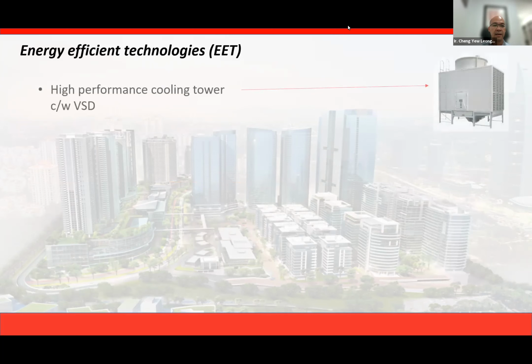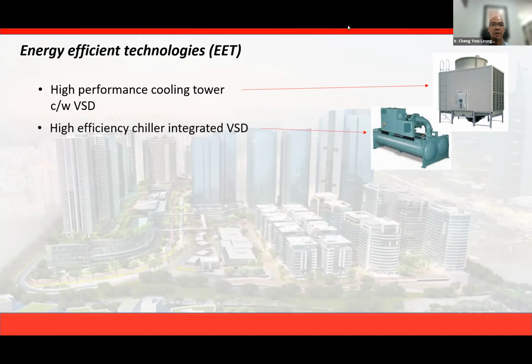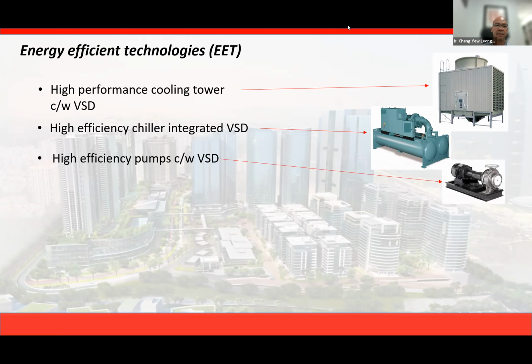Next, energy efficient technology. There are energy saving equipment such as high efficiency cooling towers, high efficiency chillers integrated with VSD, and high efficiency pumps complete with VSD as well. This VSD, variable speed drive, will ramp down the pump flow when the chiller is running in part load. This reduces energy and the electricity bill.